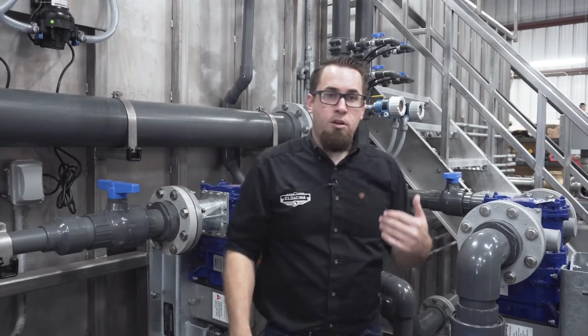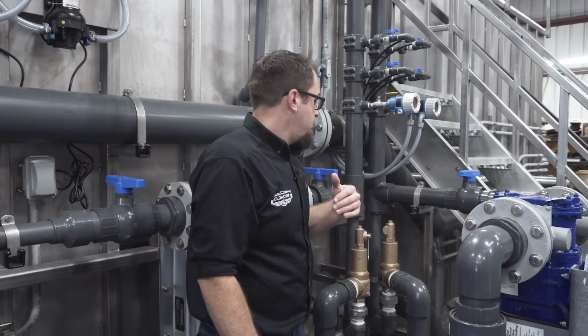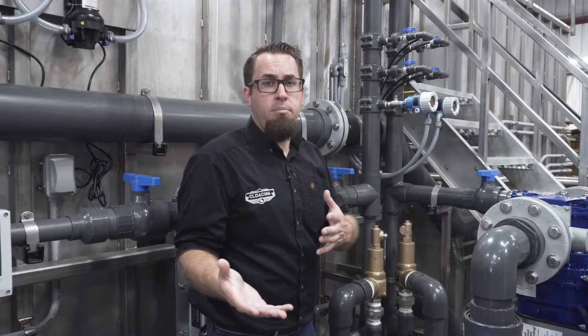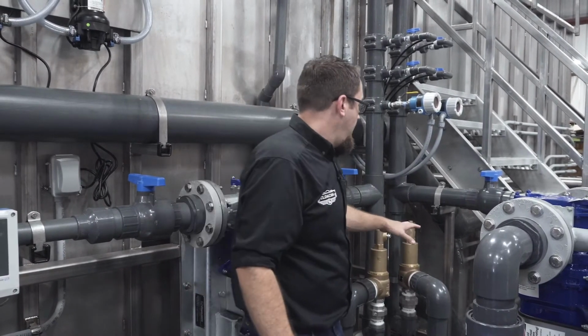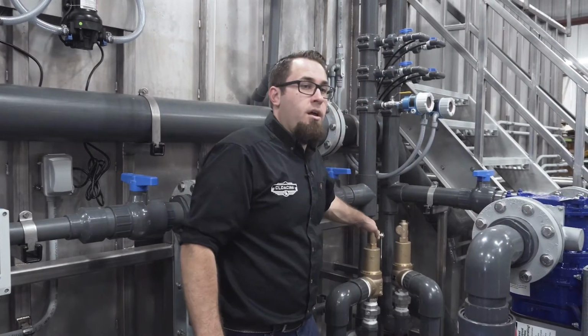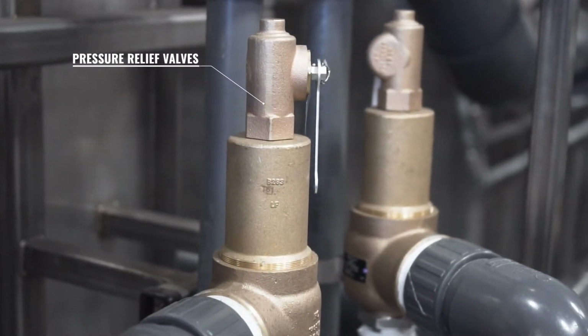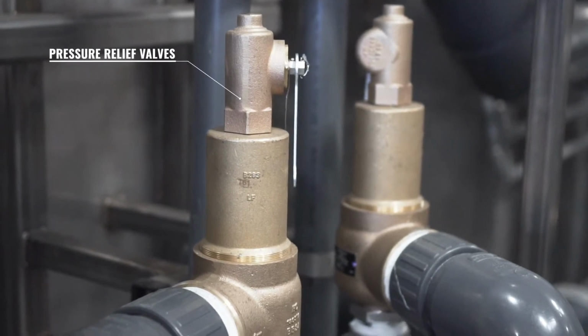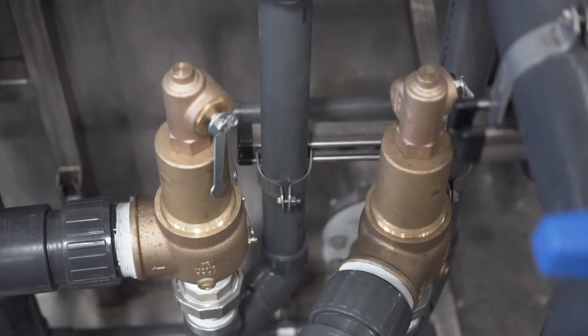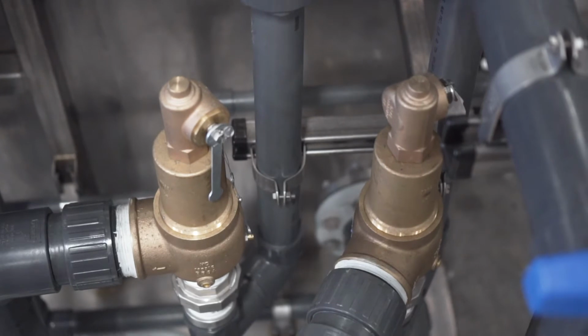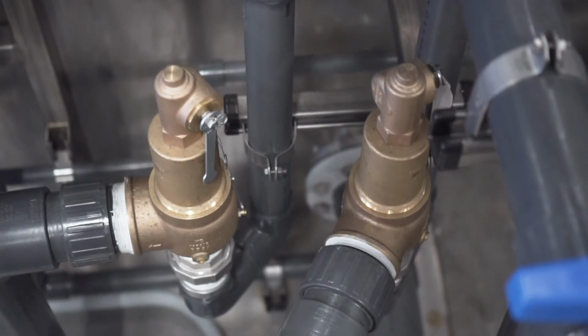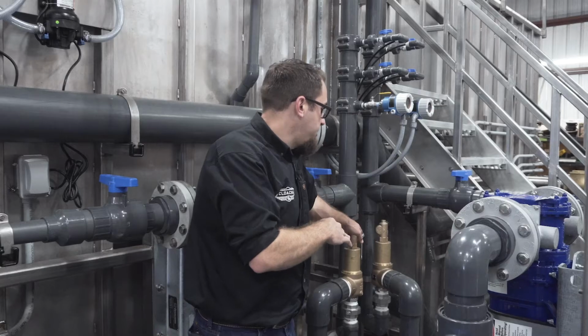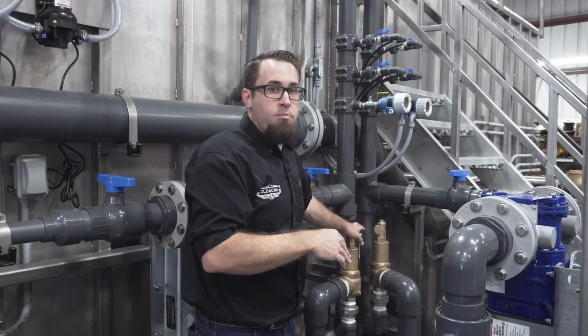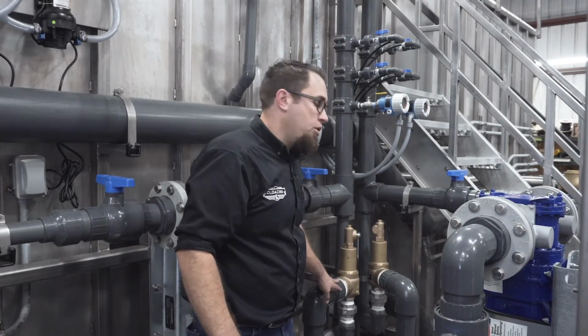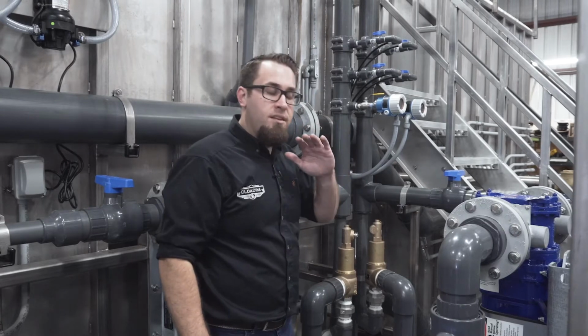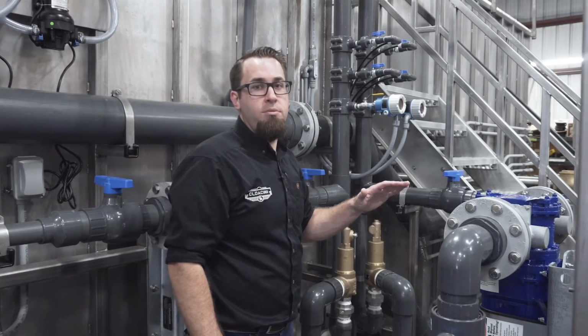Additionally, we have a complete mechanical redundancy, so that in the event that your particular membrane application requires a back pulse, we have what are called blow-off valves or pressure relief valves. They're set to just below the factory maximum TMP pressure, and the full flow blows off through these valves, which in this particular application are brass Kunkle valves, making it so that you have zero capability to overpressurize your membranes.